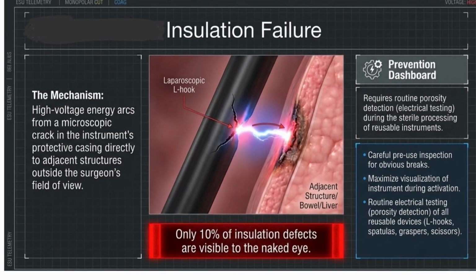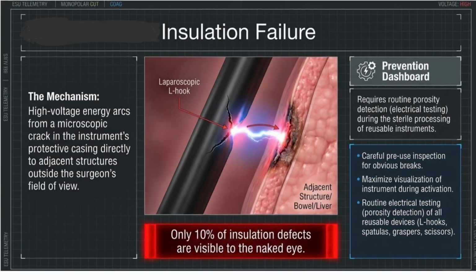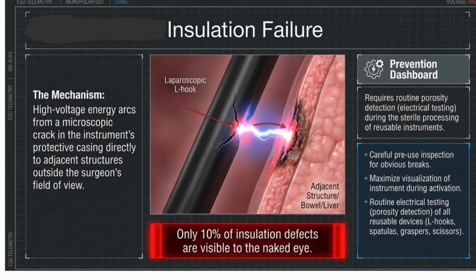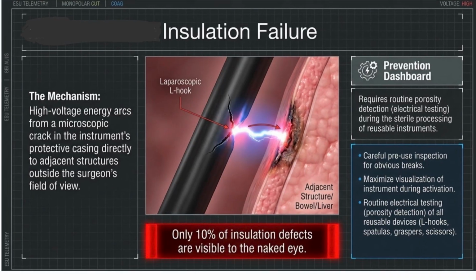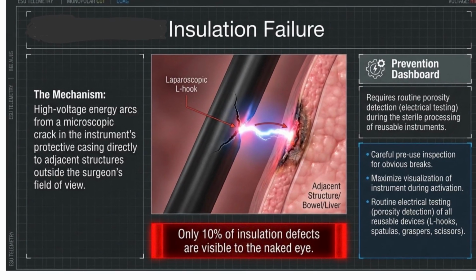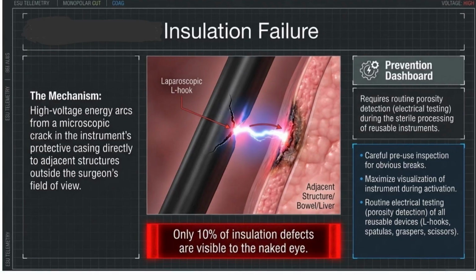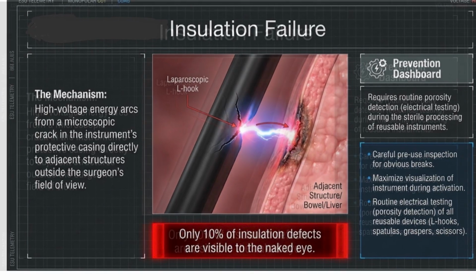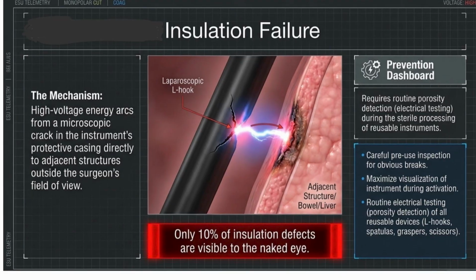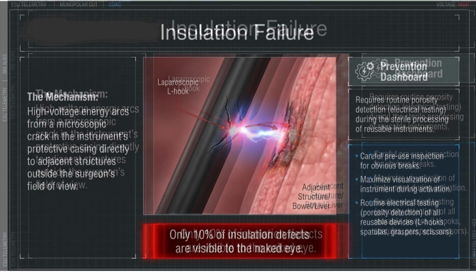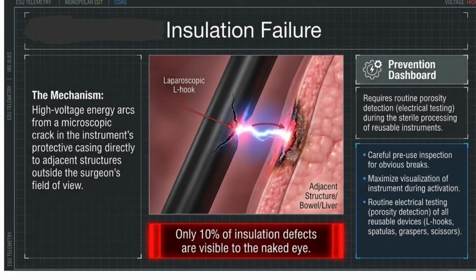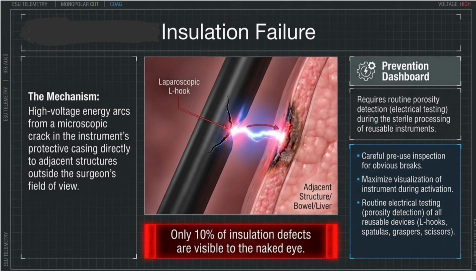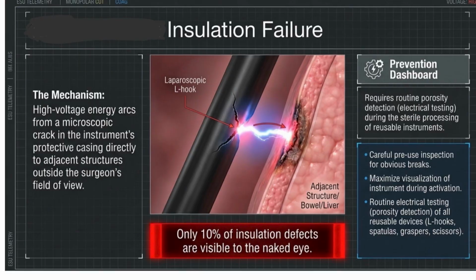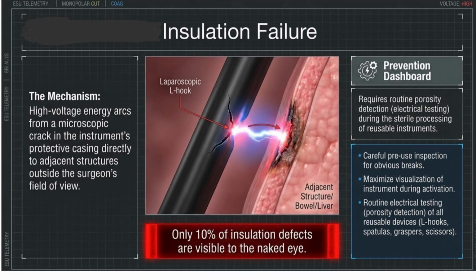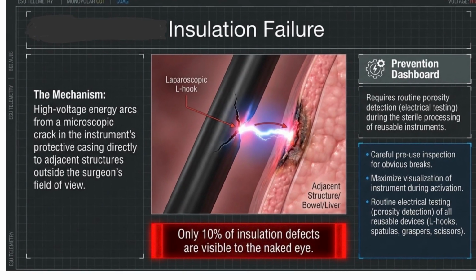Laparoscopic L hook damaged, and the current passing to the adjacent structures like bowel or the liver. Only 10% of insulation defects are visible to the naked eye. How can it be prevented? It requires routine porosity detection during the sterile processing of reusable instruments, careful pre-use inspection for obvious breaks, maximum visualization of the instrument during activation, and routine electrical testing. Porosity detection of all reusable devices like L hooks, spatulas, graspers, and scissors.